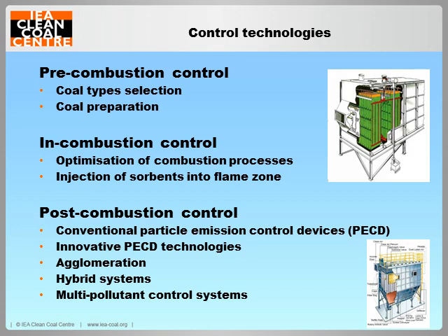PM emission control can be classified as before, during, and after coal combustion. Pre-combustion control involves choosing the type of coal and pulverising coal to the correct size. In-combustion control involves changing the burning process, for example by adjusting the combustion temperature, burning time, or boiler load, or injecting high-temperature sorbents such as limestone into the flame zone. Pre- and in-combustion control can improve the ash characteristics for downstream control technologies. To reduce PM2.5 emissions, we have to capture it after combustion.